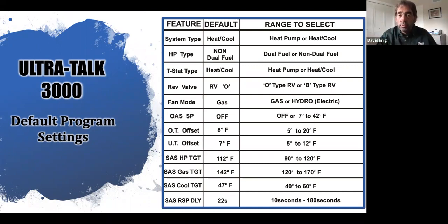So as we go down through these very quickly, we look at system type, heat cool. If I want to change it, I use the pot switches, go to heat cool, and I change it to heat pump. Any of these, I use the pot switches, navigate to that location and change it to one of the areas that you see or one of the parameters that you see on the right-hand side. Thermostat type, heat cool or heat pump. Note that all thermostats have to be heat cool or they all have to be in heat pump mode. You cannot mix and match.